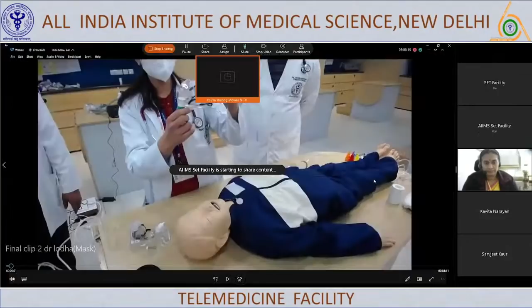The extra feature in this mask is a reservoir bag which is attached to the oxygen supply. This bag will be filled with 100% oxygen when we connect the tubing to the oxygen supply. It also has one-way valves. There are one-way valves on either side of the mask. These valves allow the exhaled air to go out, but they will not allow ambient air to be inhaled when the patient is breathing in.